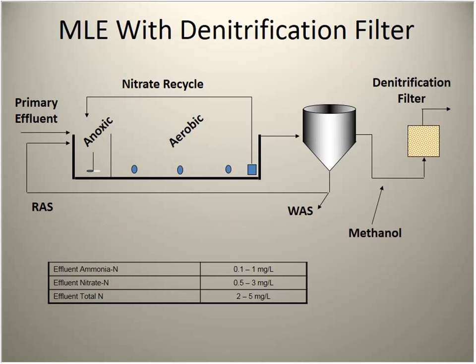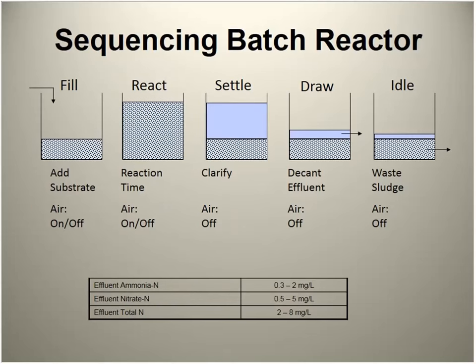The MLE with denitrification filter is a common approach in some plants — after the typical anoxic-aerobic process, a denitrification filter provides a polishing step. Methanol is added after the clarifier, and organisms living in a sand filter perform denitrification as flow passes through. Sequencing batch reactors can also be modified for nitrogen removal by adjusting their cycles — starting unaerated as the anoxic zone, releasing nitrites as nitrogen gas, then proceeding through the regular aerated process.